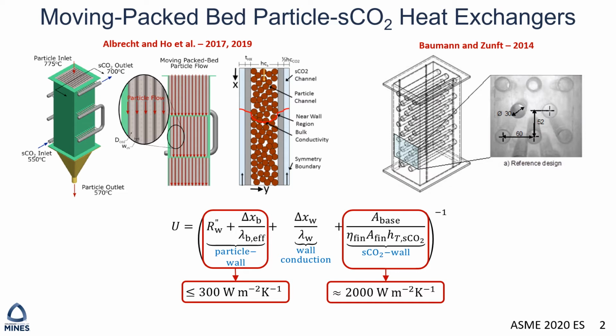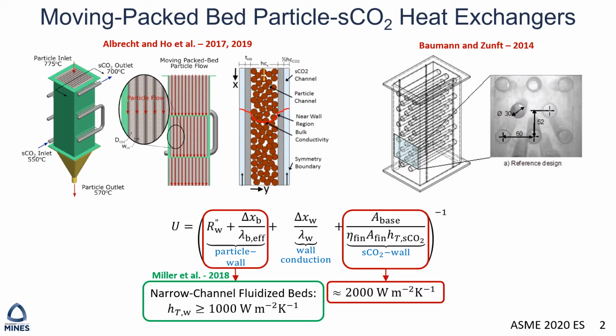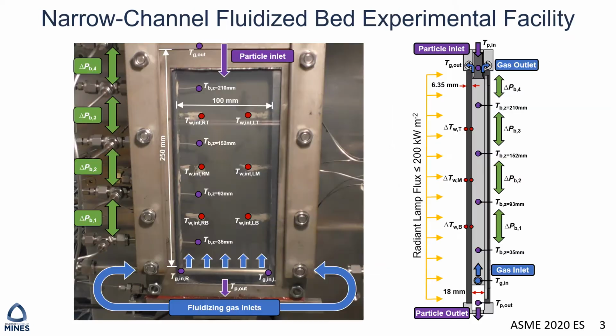This approach therefore requires large heat exchangers with short conduction length scales on the order of a few millimeters, creating significant operating challenges and making it difficult for these designs to meet cost targets for next-generation CSP plants. Prior works at Mines demonstrated that significantly higher heat transfer coefficients, in excess of 1,000 watts per meter squared Kelvin, can be achieved in small narrow-channel fluidized beds, suggesting that this approach could enable small, cost-effective heat exchangers in particle-based thermal energy storage. Towards that goal, we established a new larger-scale narrow-channel fluidized bed experimental facility.